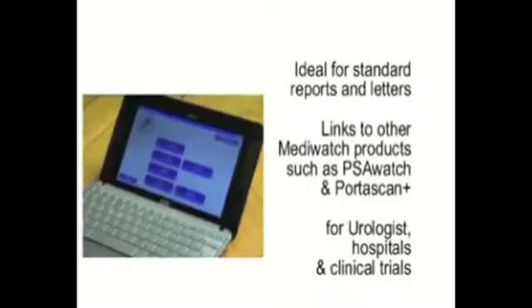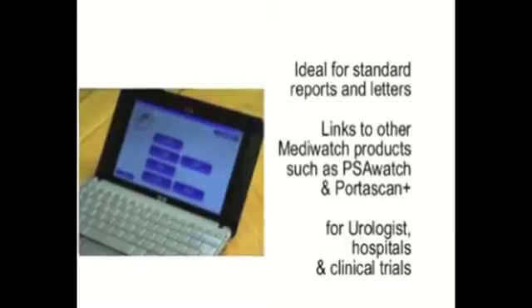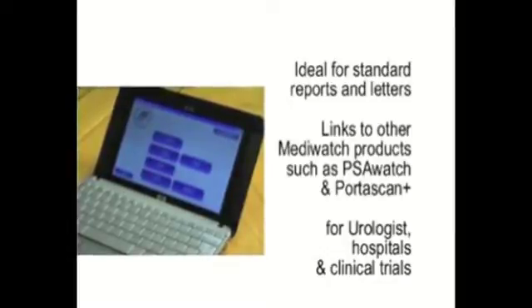Secondly, Portaflow Advanced is an advanced uroflow software application that links to its flowmeters by Bluetooth. Portaflow Advanced can be installed on any PC, laptop or desktop. Recommended for users who require standard reports, letters, flexible data extraction, and users who integrate reports with other MediWatch products such as PSA Watch or Portascan+.